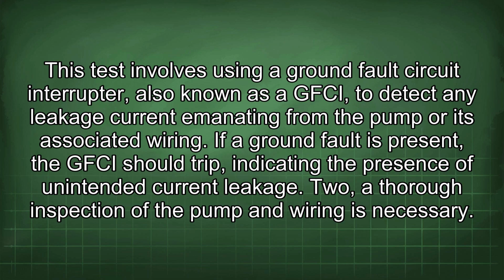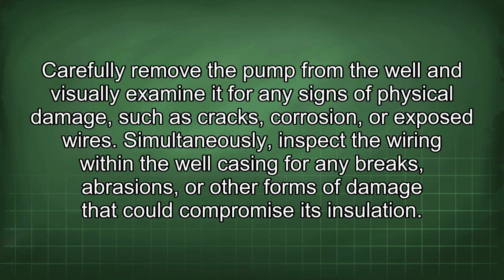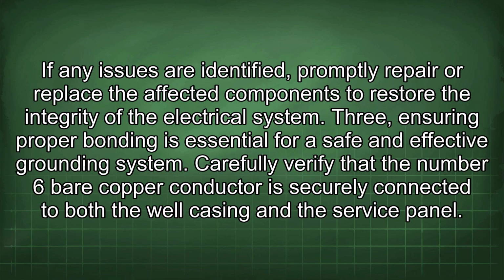2. A thorough inspection of the pump and wiring is necessary. Carefully remove the pump from the well and visually examine it for any signs of physical damage, such as cracks, corrosion, or exposed wires. Simultaneously, inspect the wiring within the well casing for any breaks, abrasions, or other forms of damage that could compromise its insulation. If any issues are identified, promptly repair or replace the affected components to restore the integrity of the electrical system.